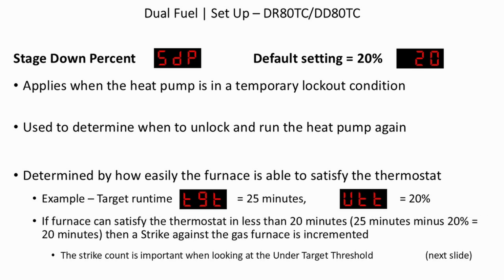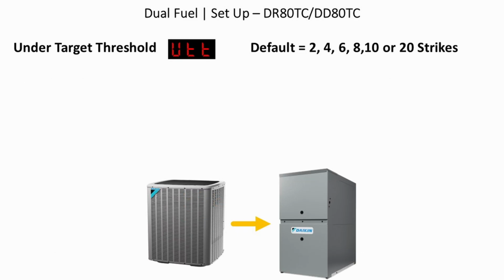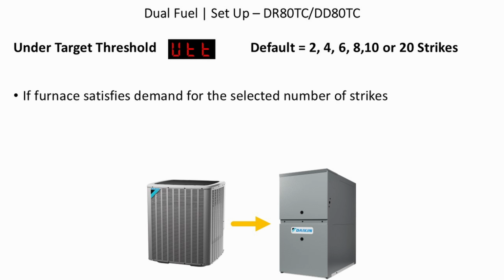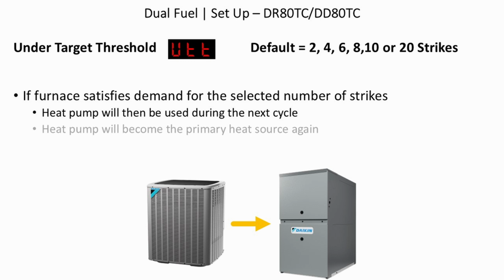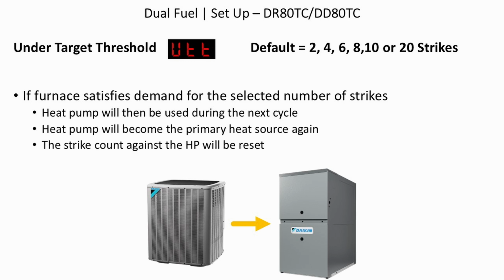The strike count is important when looking at the under target threshold. Under target threshold, UTT, default is 2, 4, 6, 8, 10, or 20 strikes. If the furnace satisfies demand for the selected number of strikes, then the heat pump will be used during the next cycle. The heat pump will become the primary heat source again, and the strike count against the heat pump will be reset.